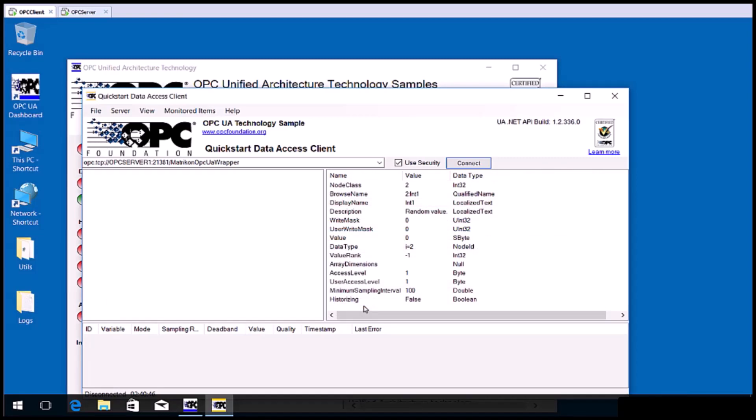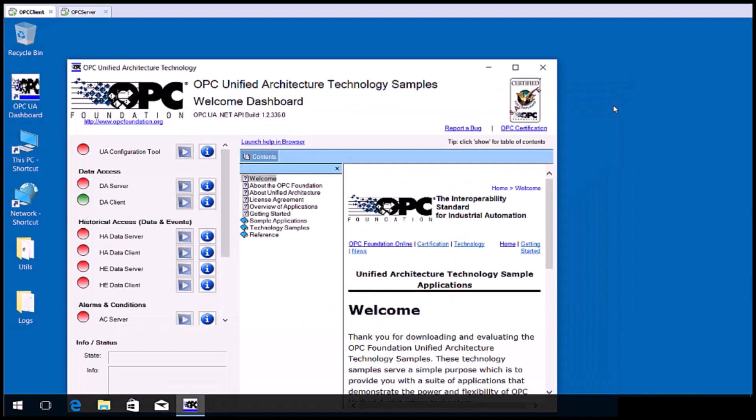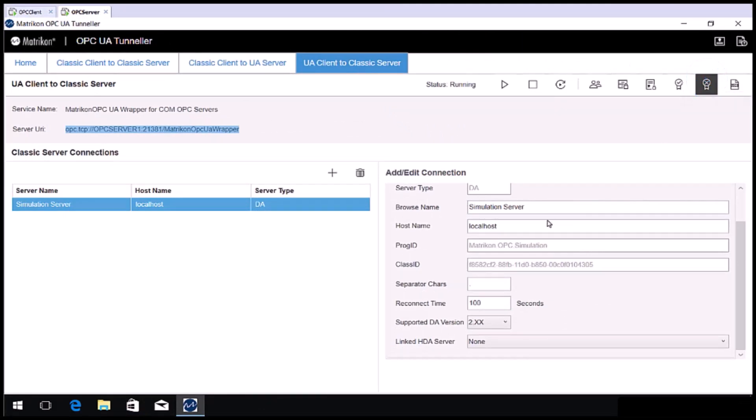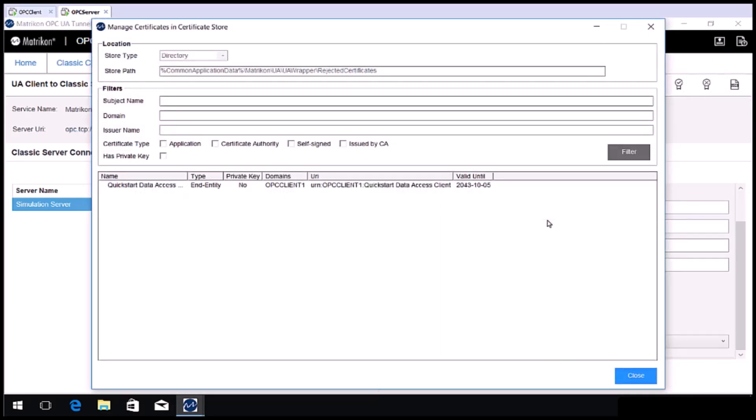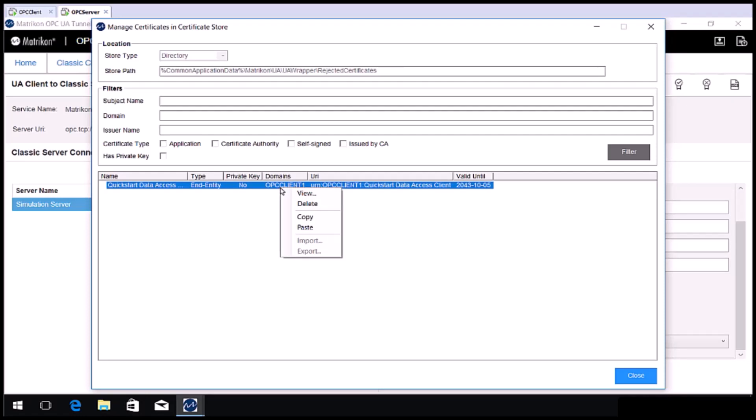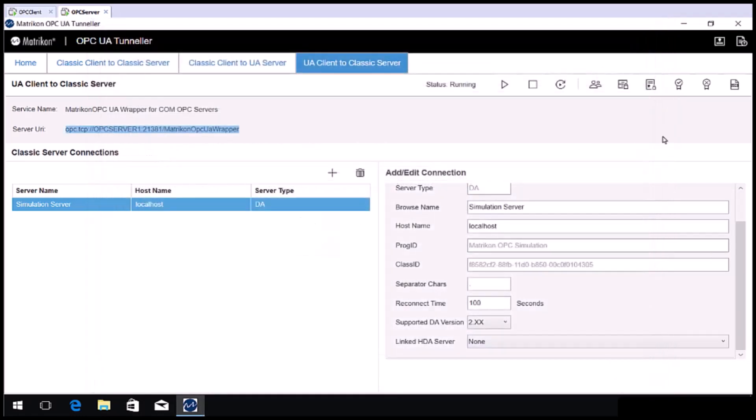Close the OPC UA client. Go back to the OPC server side. The Tunneler configuration GUI should still be open. Open the rejected certificates. You can see there is a rejected certificate from OPC client 1 in this list. We have tried to access this OPC UA server with a client for which a certificate is not known, so Tunneler has rejected the request and placed the received certificate in here. Right click on the entry and choose copy.